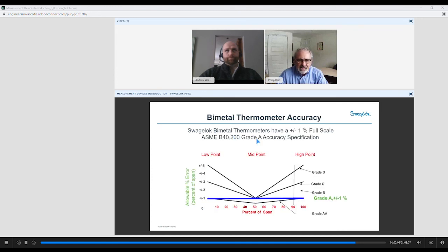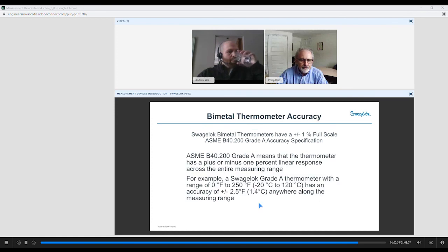Again, accuracy grades, ASME B40.200: grade A accuracy means that across the whole scale of the thermometer, this accuracy will be maintained at plus or minus 1% of scale. If you were using grade D, for example, plus or minus 5%. But also, thermometers, like pressure gauges, have the most accuracy right at the midpoint. Okay?